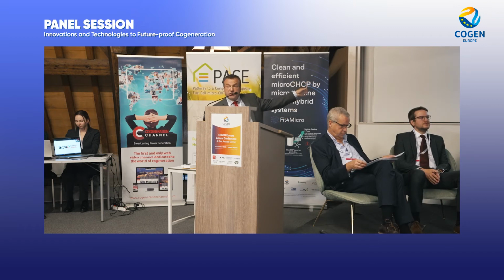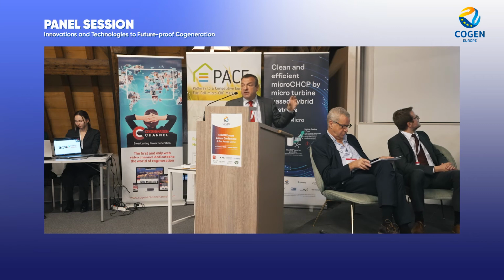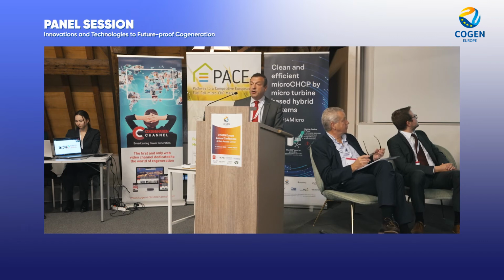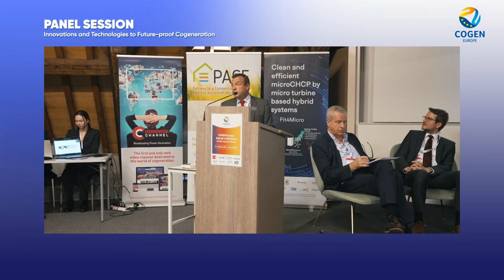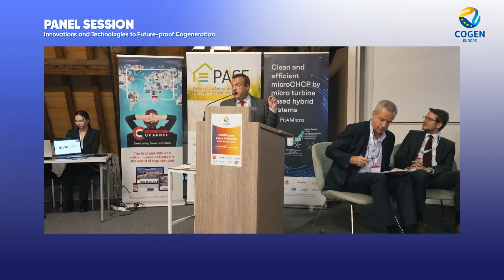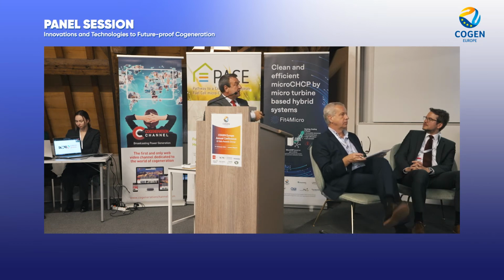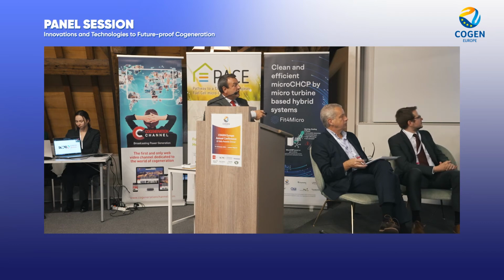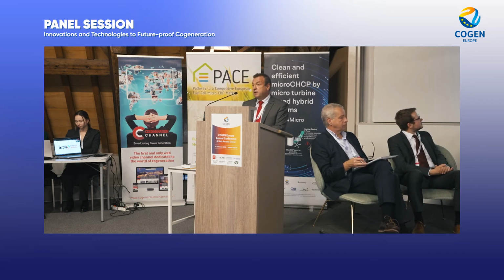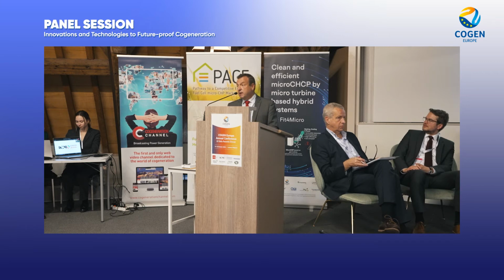We have modules of 12 meters length and 0.5 by 0.5, and what we do is connect them in a smart way to produce what we want. In the yellow pipes, normally we put the hot fluid—it can be any hot fluid, from hot oil, flue gases, even electricity through heat resistances. In the center pipe, we heat the fluid we want—normally water, and at the end we obtain saturated steam. We can reach up to, when charging with electricity, steam at 600 degrees and 100 bars, and from that we can go to lower values.